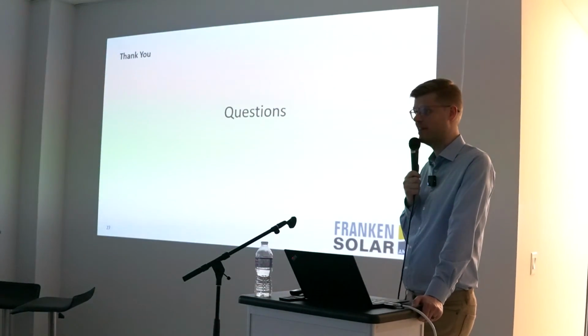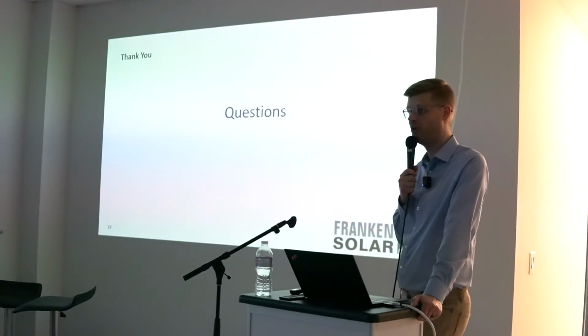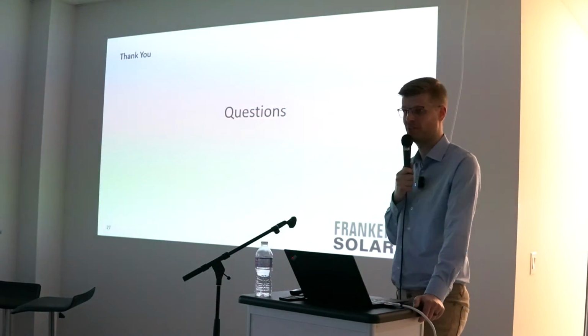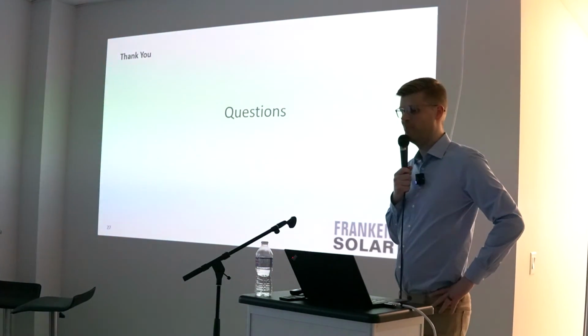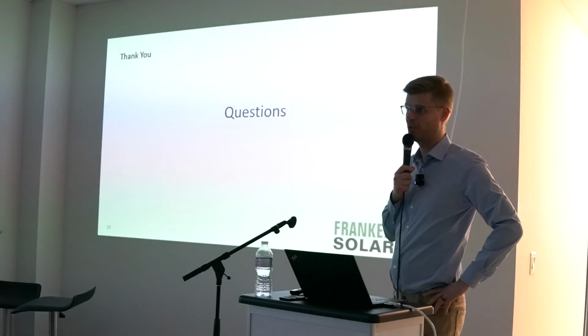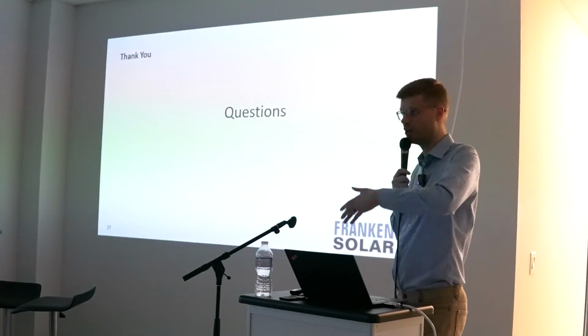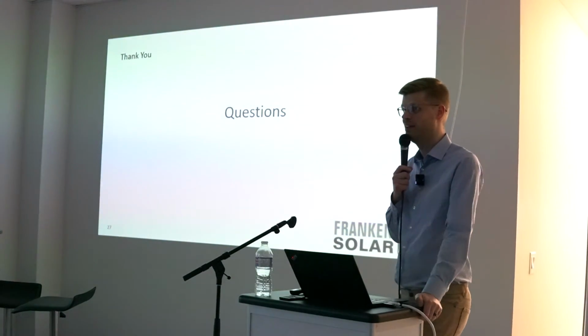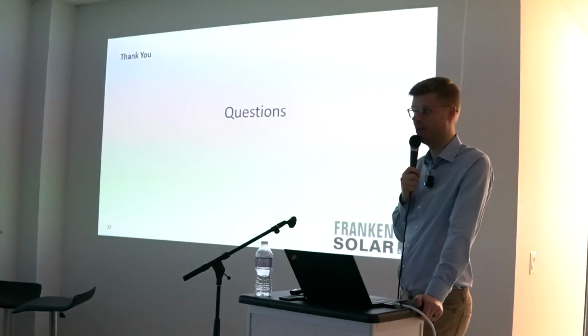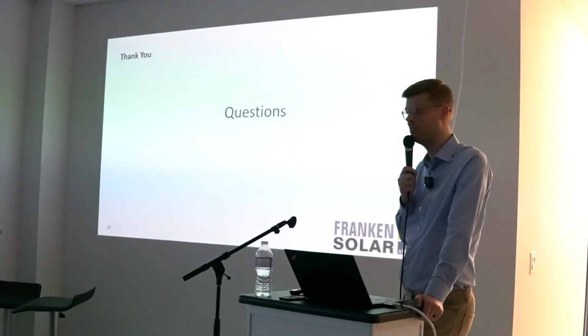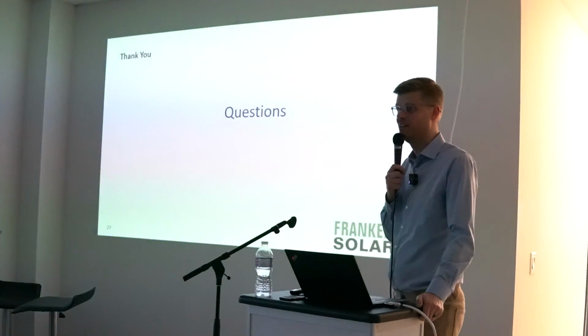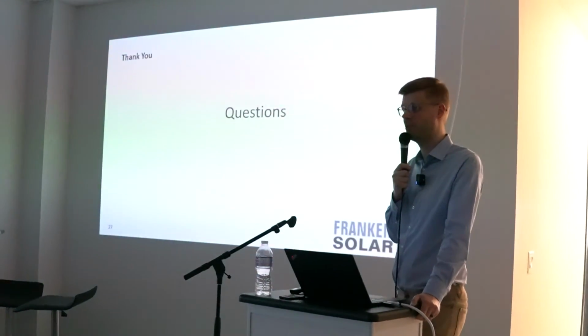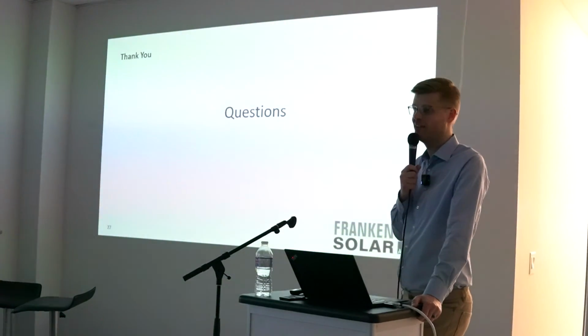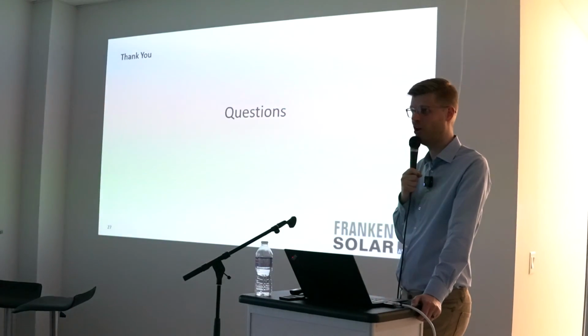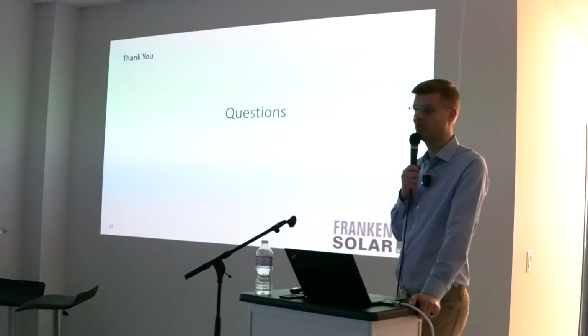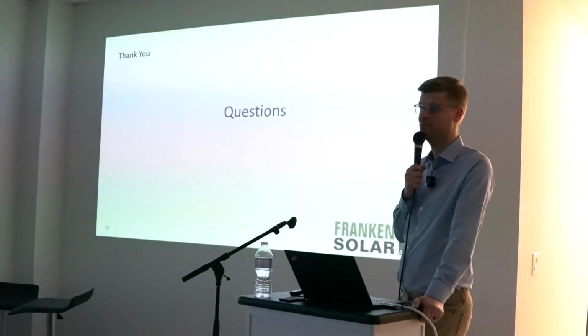It's pretty much all lithium ion. When it comes to the Canadian market and off-grid, we're still facing extremely low ambient temperature, specifically for cottage systems that are maybe not heated year-round. There, a lithium ion chemistry is still very challenging when it comes to the storage part of it, as well as the charging part in very low temperature environments. There's no good solution on the market. There are some chemistries that are a little bit better than typical standard lithium iron phosphate. LTO cells, for example, can have very low storage temperatures and charge and discharge. It's not really commercially available at scale and cost effective, but for most of those systems, lead acid will still play a role in that specific application.